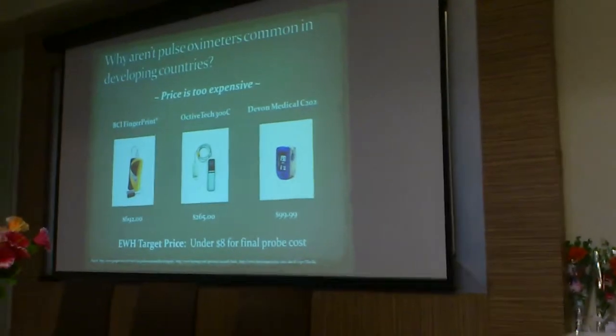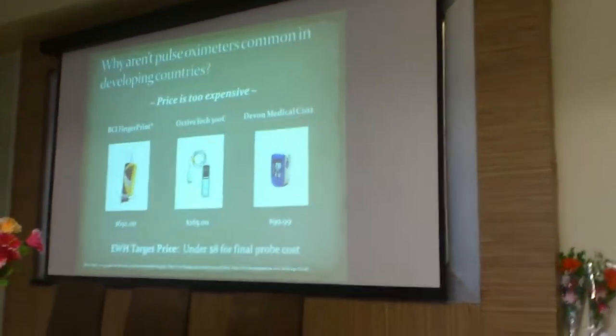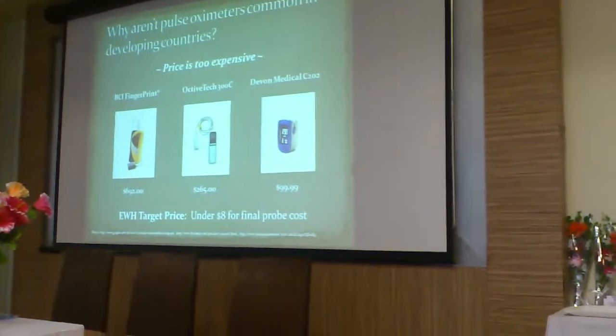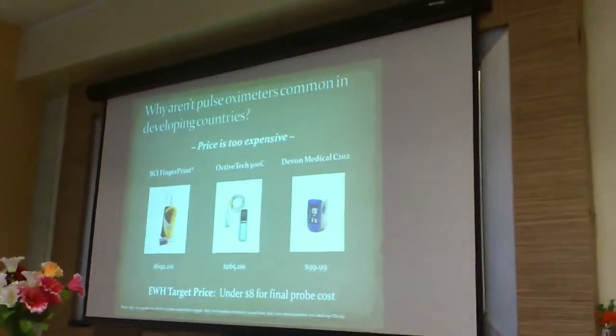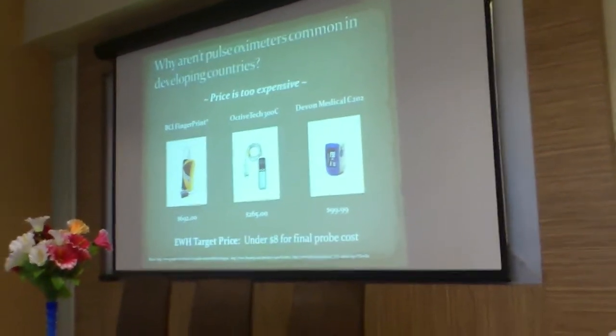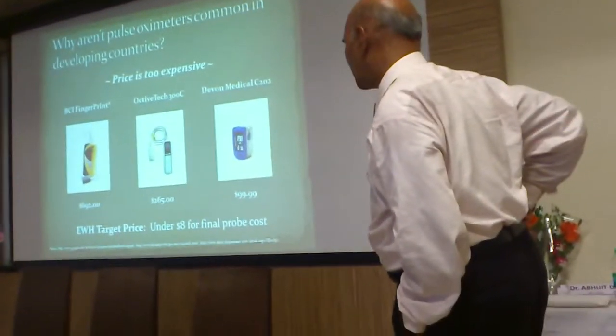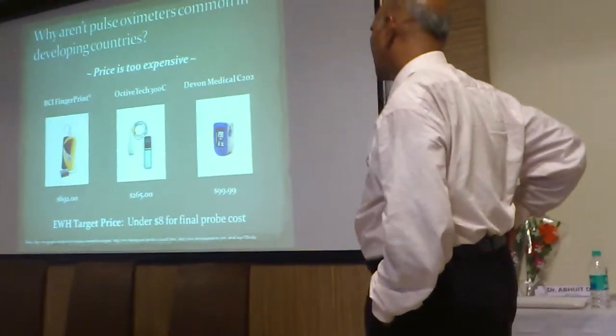These are the typical pulse oximeter models common in developing countries. There is a company called BCI, the BCI FingerPrint model, the OctiveTech 300C and the Devon Medical C202. You can see the price ranges — about $670, $265, and as low as $99. It's just a clip which you put on the fingertip and you have two readings: one is oxygen saturation level, which is 98, and you also have the pulse rate at about 75.